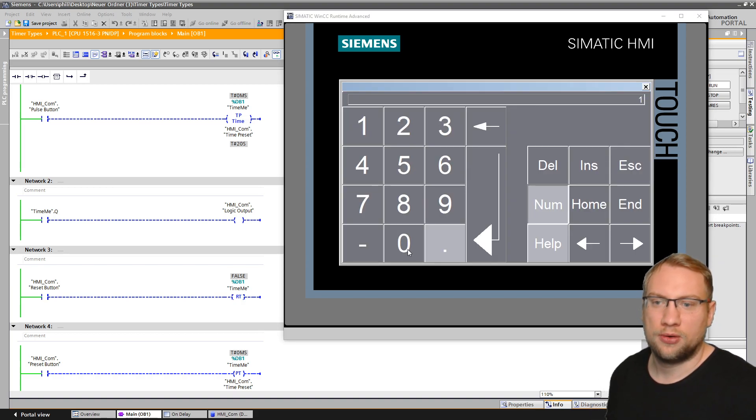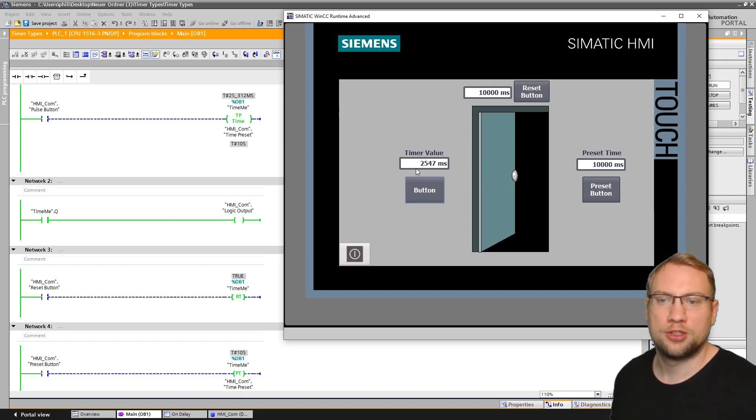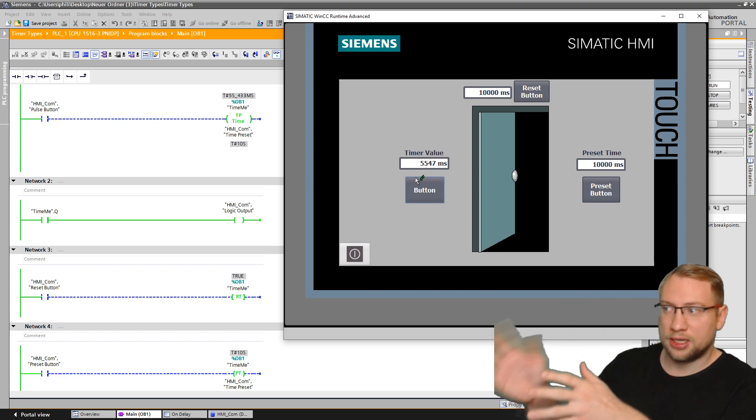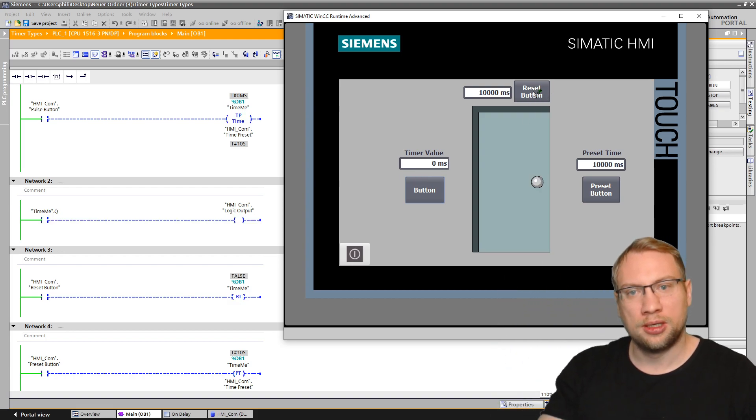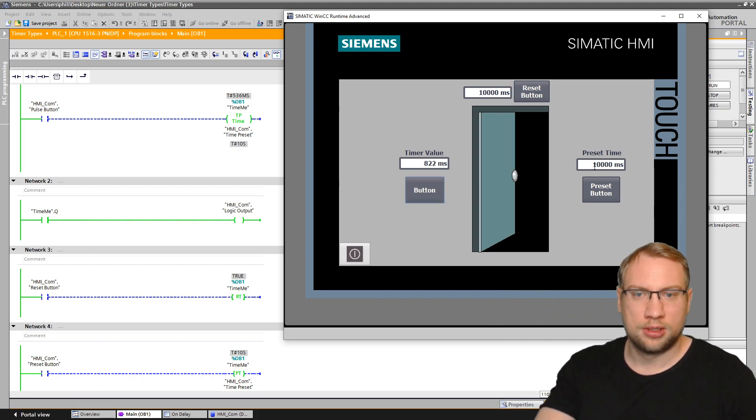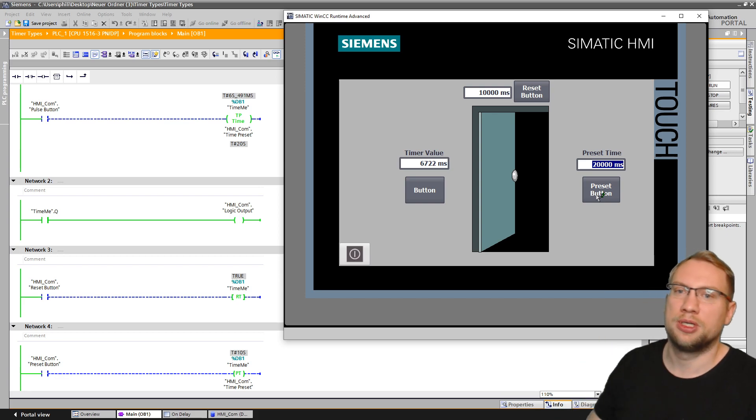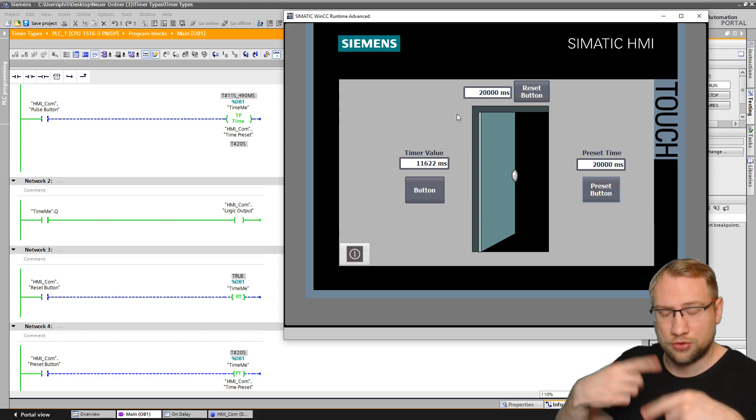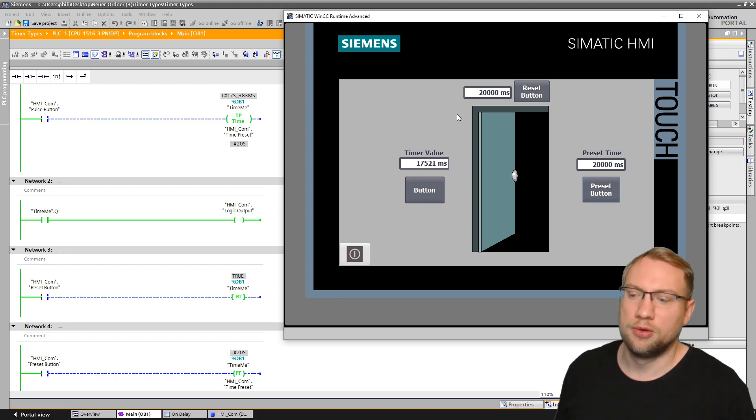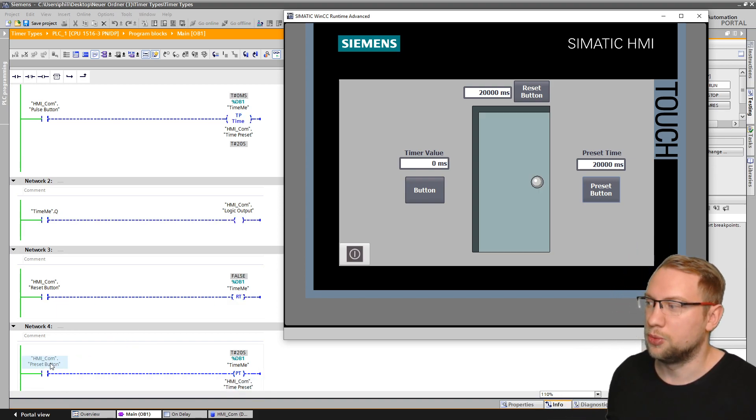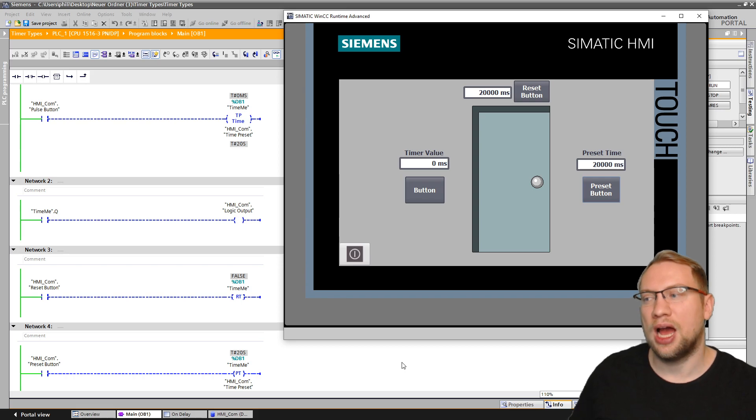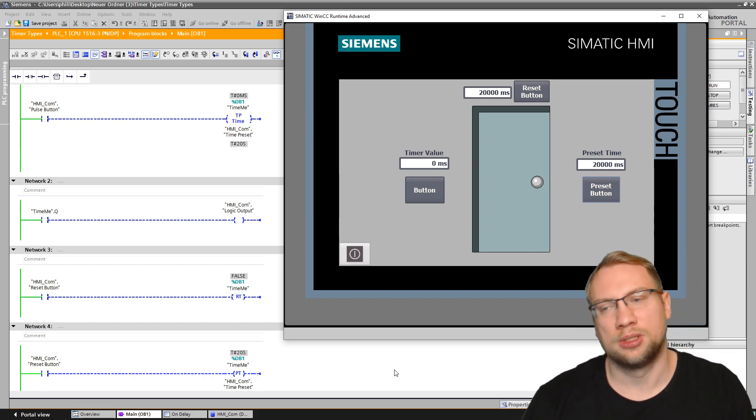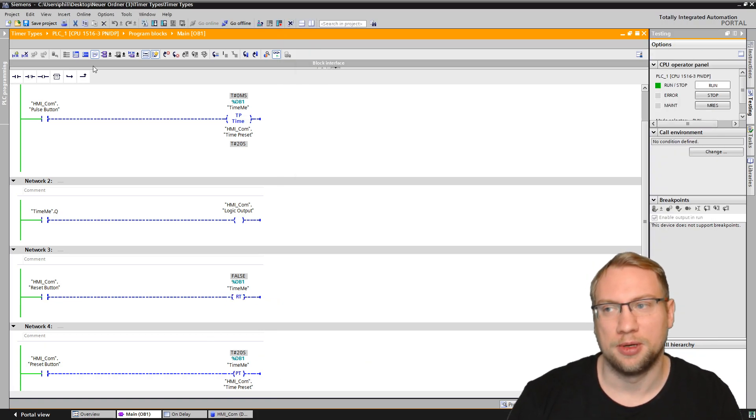And what I can also do, if the timer is running right now, the timer is running, two, three, four. And at second number seven or so, I realize I need 20 seconds actually. The door needs to be open longer. I can't just change it here. The program will realize but not apply it. I have to press preset button. And now you see the timer has actually loaded that value, even when it's running. And now we're going to 20,000 instead of 10. That's called the preset. We're changing the preset even when the program is running. And that's what we're doing with this little network down here. Those are two extended timer operations that we can use when working with TIA portal with the IEC standard timers, the reset timer and the preset timer.